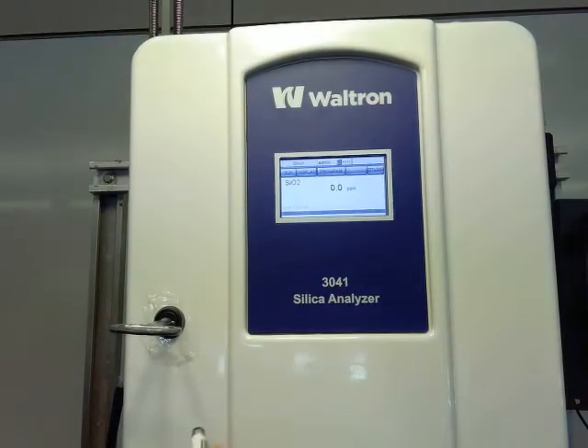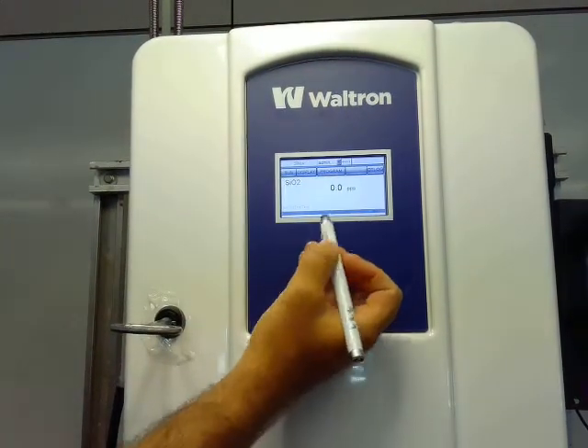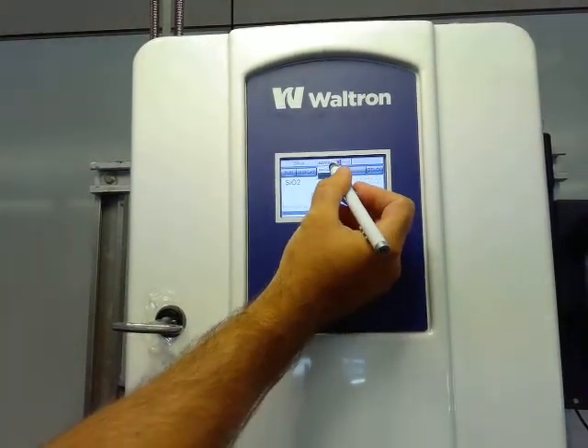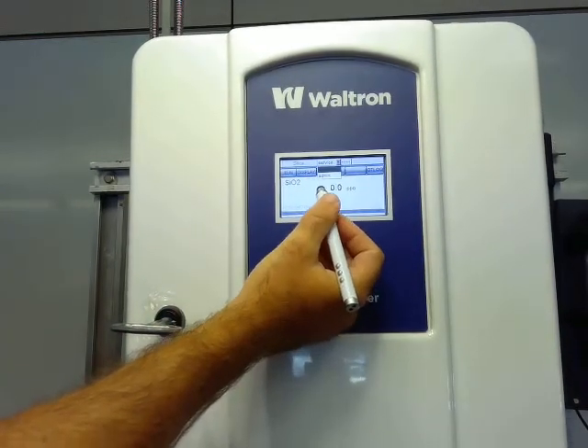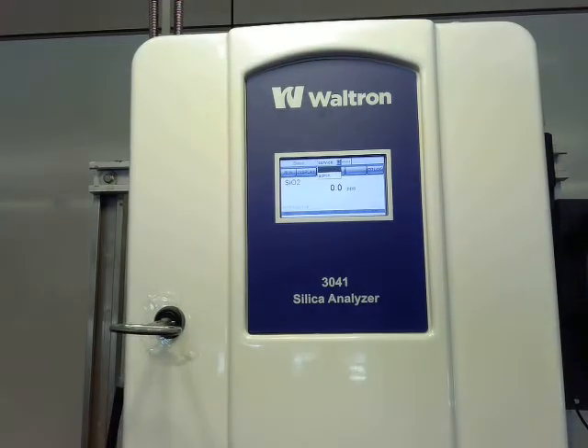So now that we've finished our calibration, if we wanted to check what our actual calibration factor was that we calculated, we would need to log in with the password. So there's two password levels. We have a service password and an admin password. The service password is in the manual, and it's 4 ones. The admin password is not printed in the manual, but the password itself is 6699, and if you need it for any reason, we're certainly willing to give it out.